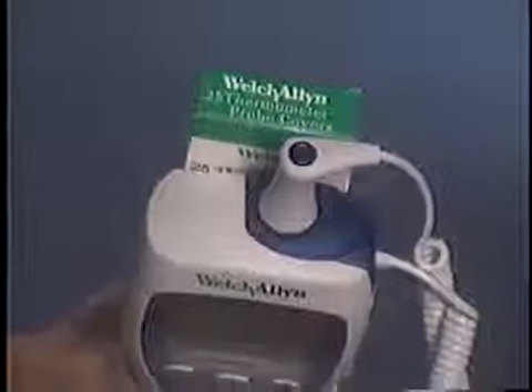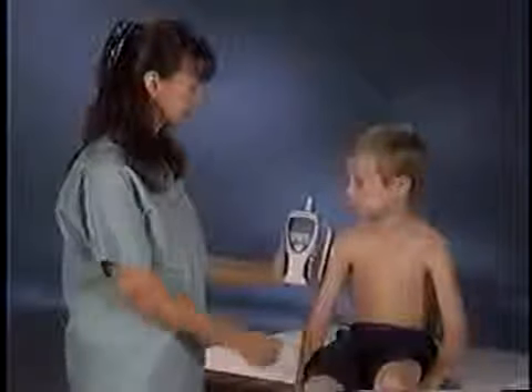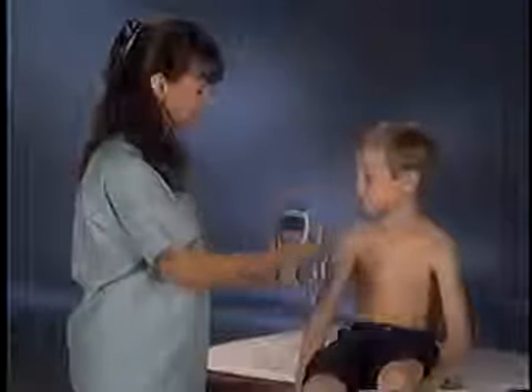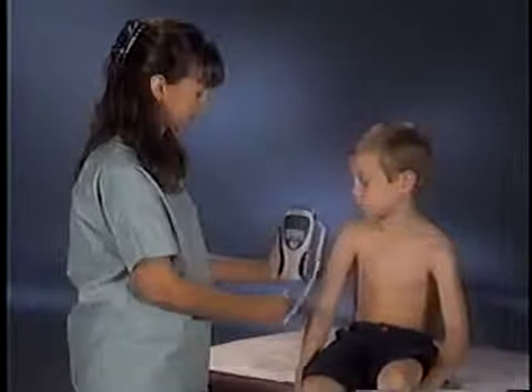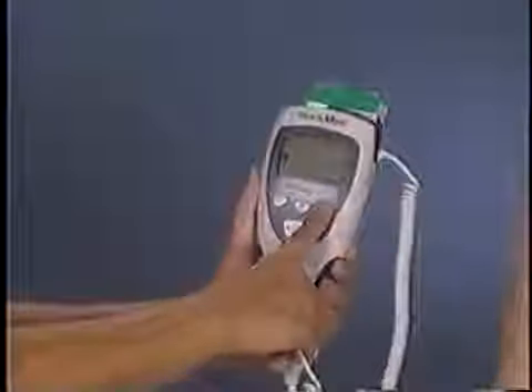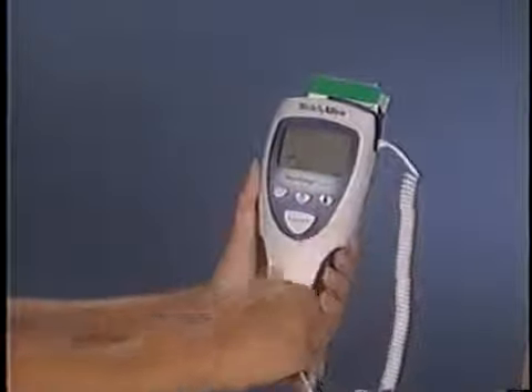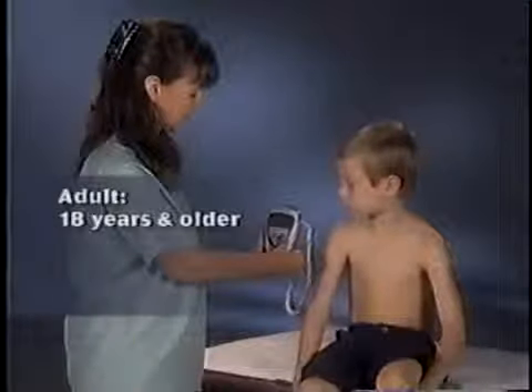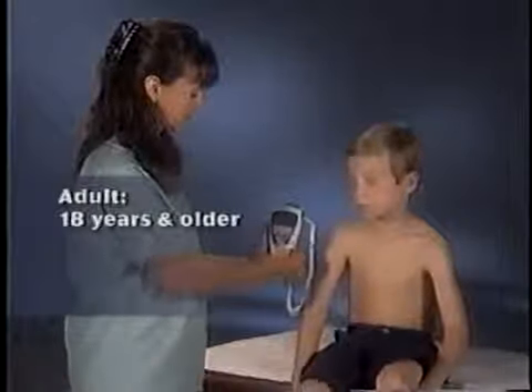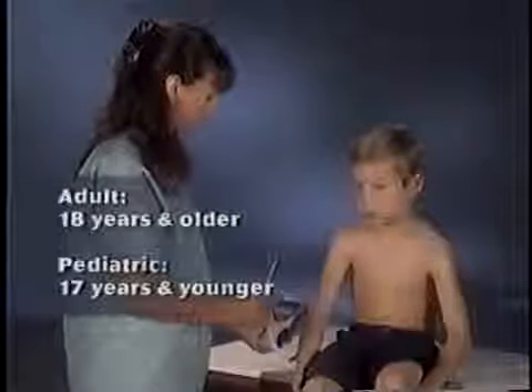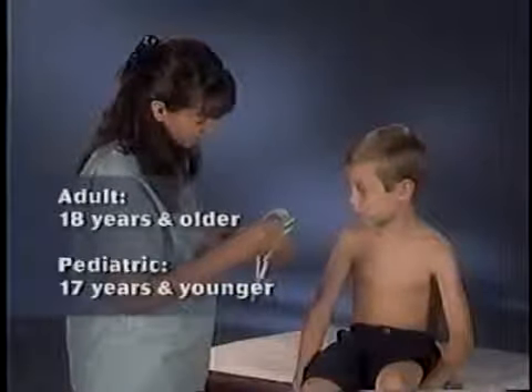Use the probe with the blue ejection button and the blue probe well when taking an axillary temperature. Remove the probe from the well and verify that the correct axillary mode is selected. If not, press the Mode Selection button until the correct indicator appears. Adult axillary mode for patients 18 years and older, and pediatric axillary mode for patients 17 years and younger. Insert the probe into a Welch Allyn probe cover, pressing the probe handle down firmly.